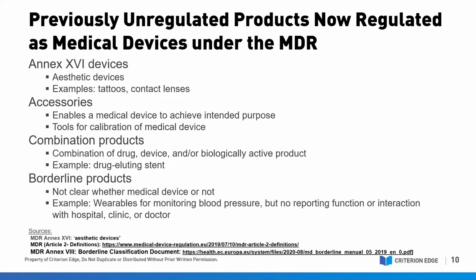An accessory to a medical device is defined by the MDR as an article which, while itself not being a medical device, is intended by its manufacturer to be used together with one or several parts of medical devices to enable the medical device to be used in accordance with its intended purpose, or to specifically and directly assist the medical functionality of the medical device in terms of the intended purpose. So a few examples of that would be tools for calibrating medical devices, special supports, or even remote controls for operating tables. The third group here are combination products.